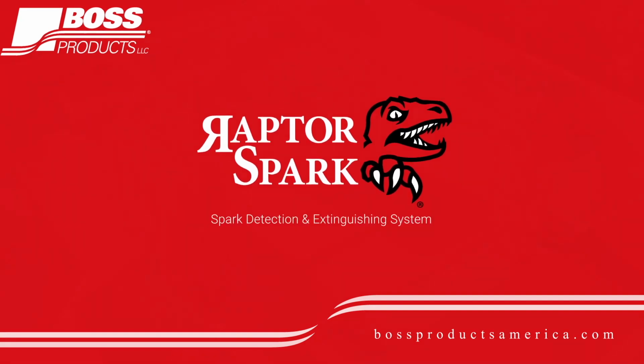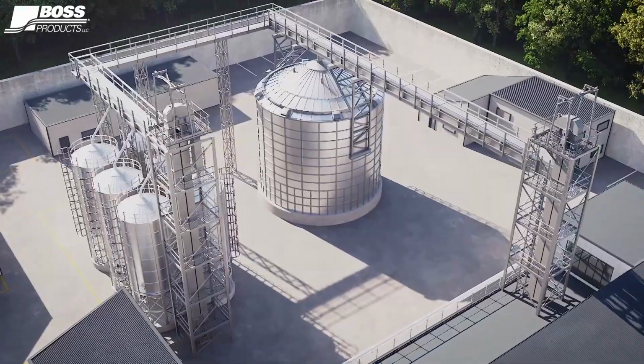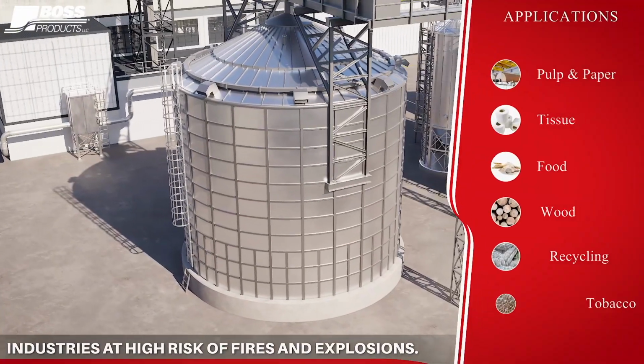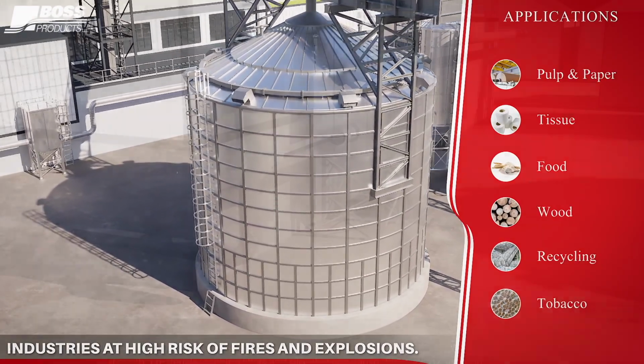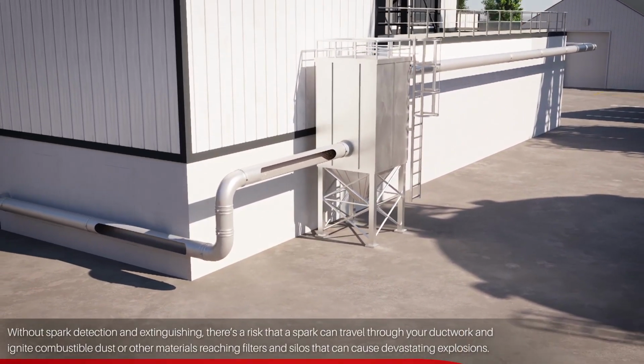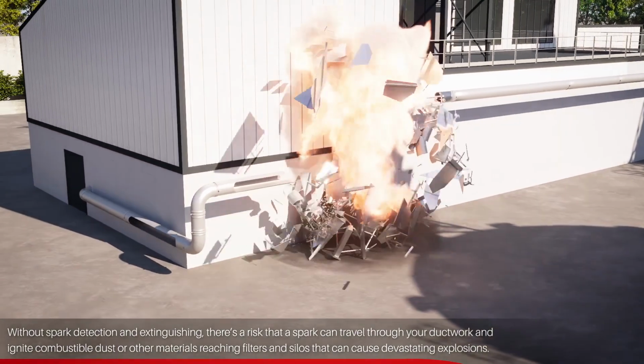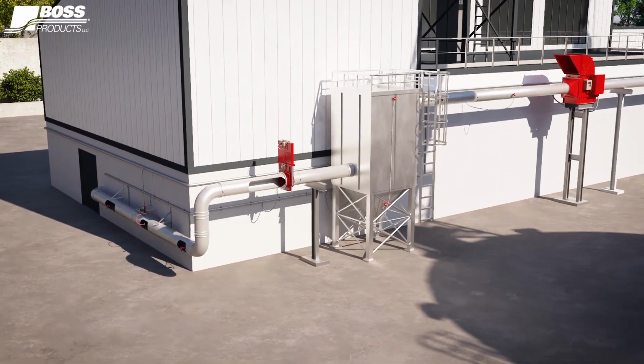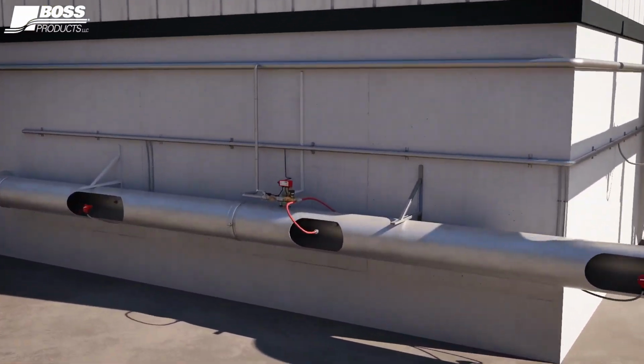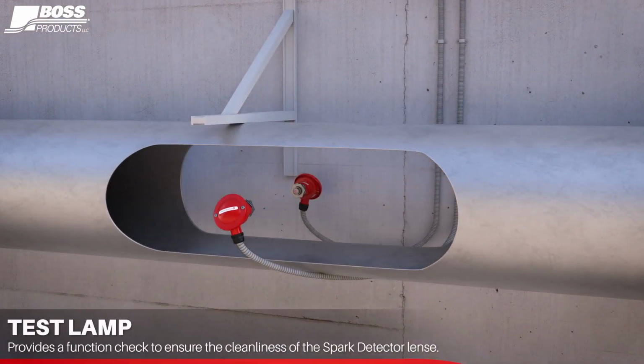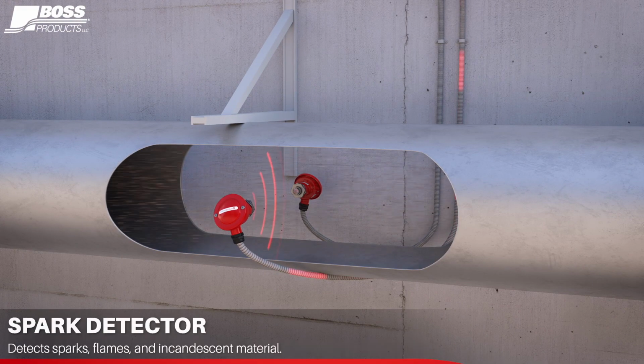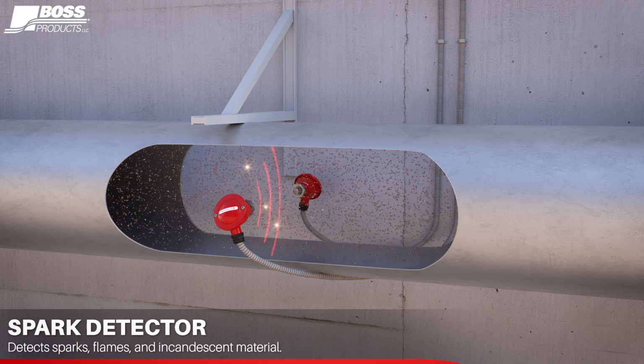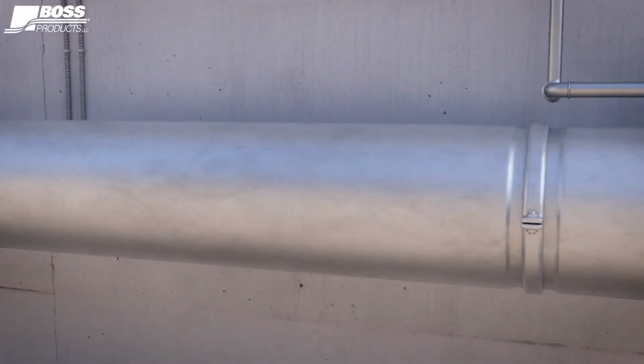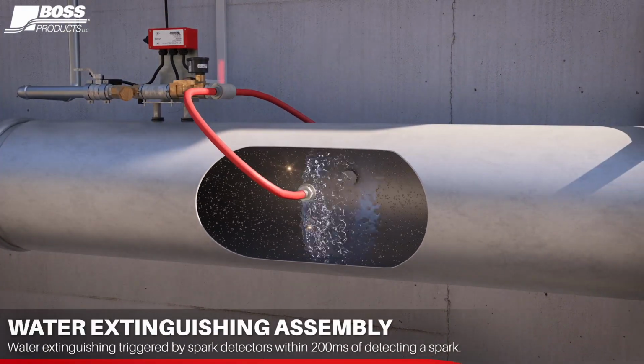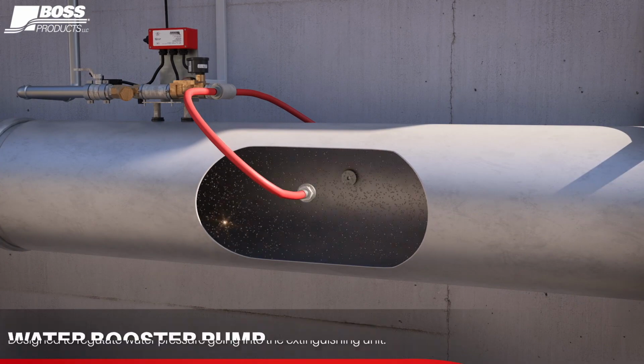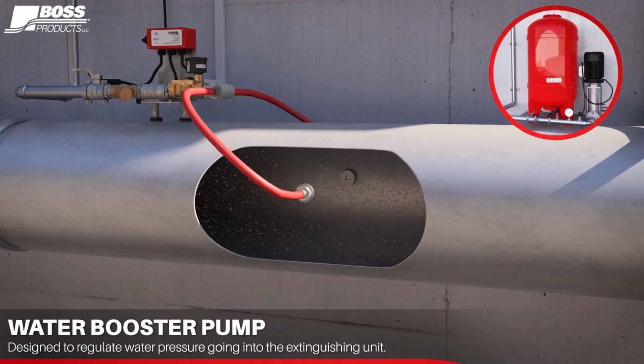So here's a little video of some of our products and solutions with our spark detection and extinguishing. Different applications that we can work with: pulp, paper, tissue, food, wood, recycling, tobacco. Spark detection is basically where a sensor is installed in the ductwork, and when there is a spark that passes by, it'll send a signal back to a control panel that will tell an output device of some sort, whether it's water extinguishing, a mechanical fire break shutter, an abort gate, to trigger and basically mitigate the potential for a fire. So in this case, they're showing water extinguishing, which is something we can do as well, and provide booster pumps too.